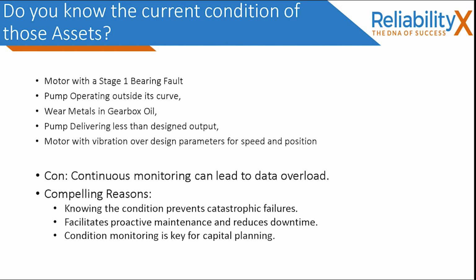You can monitor these periodically. You can do vibration analysis quarterly, check pump curves every year, do wear metal analysis on lubrication samples every 3 months worth of runtime hours, and check a pump delivering less than optimal output just by pressure readings. So these things don't need really complex monitoring schemes applied.